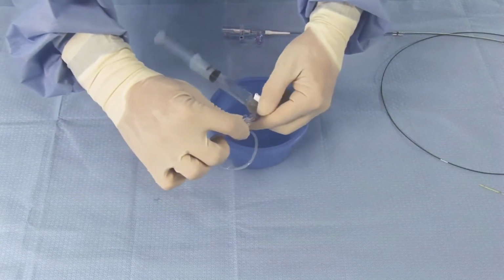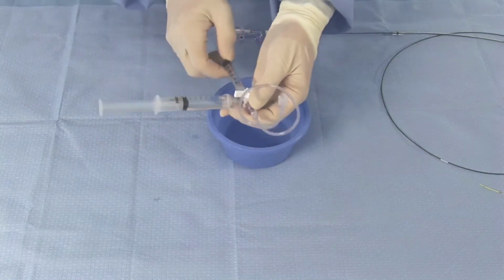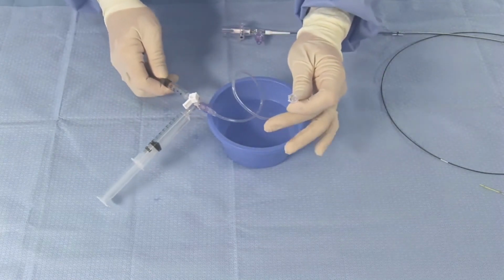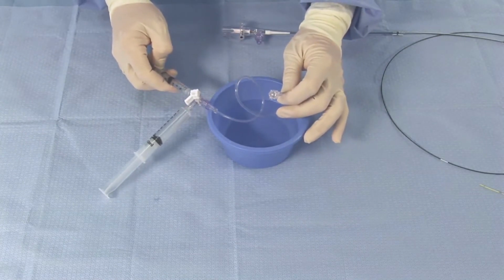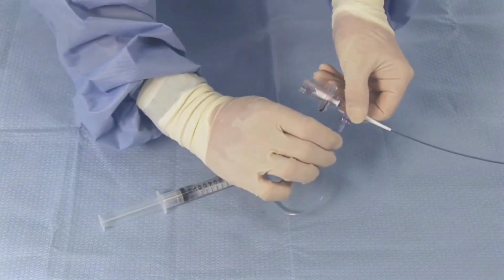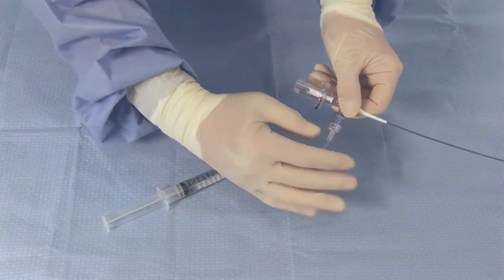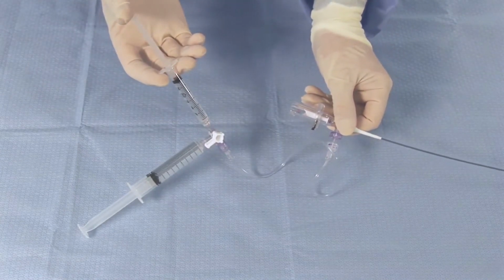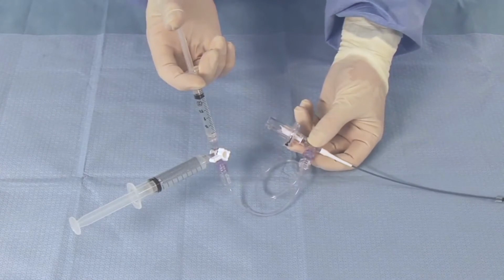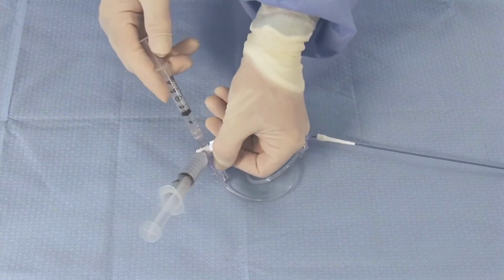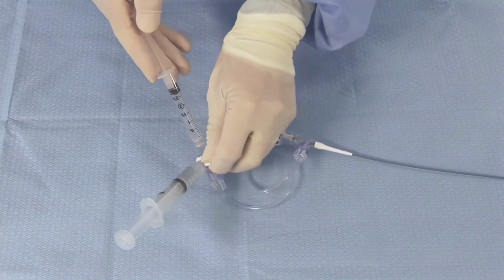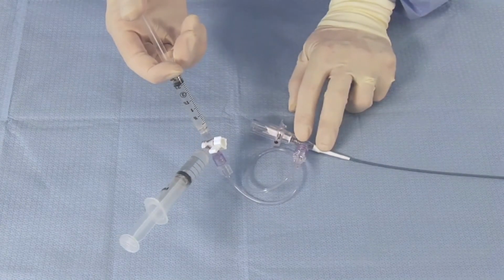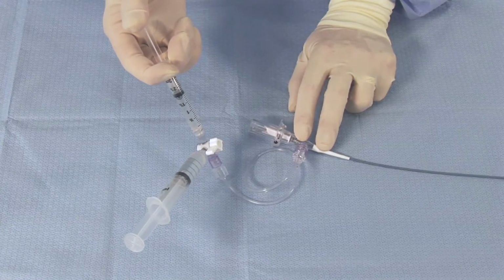Then connect the assembly to the extension tube and use the 3 cc syringe to flush the extension tube in order to expel all air from this assembly. Connect the extension tube to the one-way valve on the catheter hub. The 10 cc syringe is to be used as a reservoir for refilling the 3 cc flushing syringe. Flush the catheter continuously using the 3 cc syringe until all bubbles are expressed from the clear distal shaft. Refill the 3 cc syringe with the 10 cc syringe. Alternatively, you may flush twice with the 3 cc syringe. Apply steady but not excessive pressure while flushing.